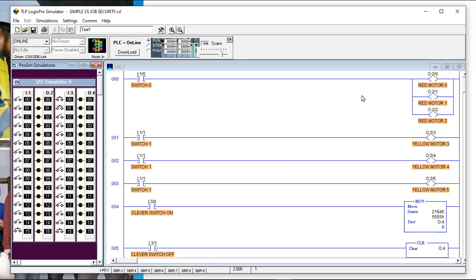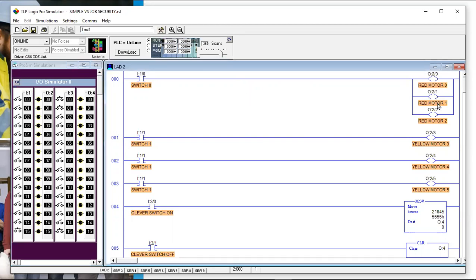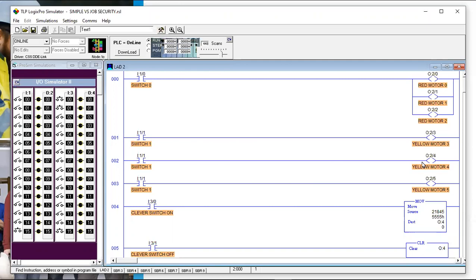If we know what it's called we could also search for 'red motor one' by name, as long as we know what it's called. When troubleshooting we'd say: what's causing it to not come on? If there were 15 different conditions that had to be satisfied in this rung of logic, we could look and see which one wasn't true. Even with 20 different things that might keep a motor from running, we can find the problem very quickly — it's the one that's not true.